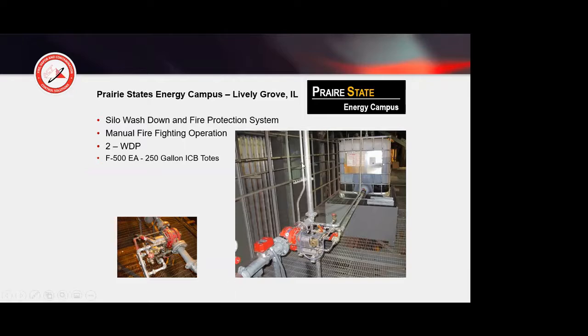But as this system runs, the agent comes through the pipe and gets proportioned right here. So what you end up with, this is plain water, this is 100% concentrate, and then going up to this would be, in this case, a 1% solution. And in this application, this is feeding a sprinkler. It's a hybrid washdown fire protection system in the silo, as well as feeding a standpipe up in the tripper room to accomplish some washdown.